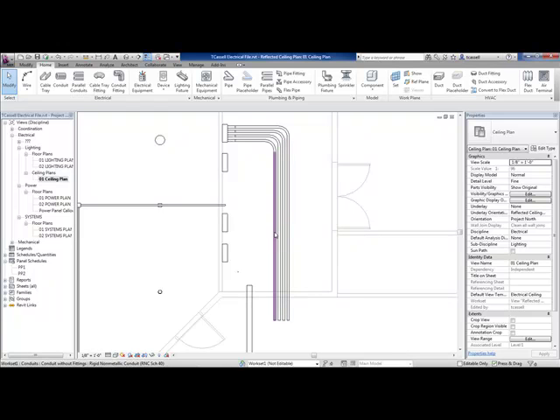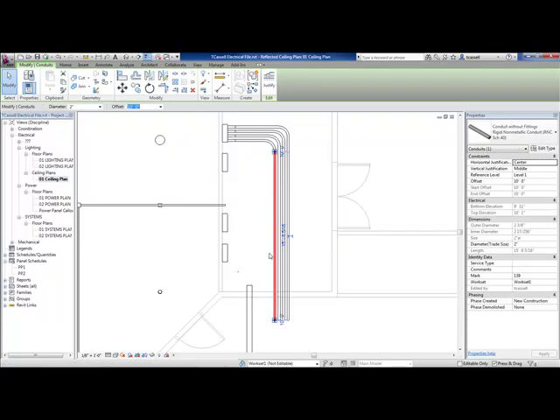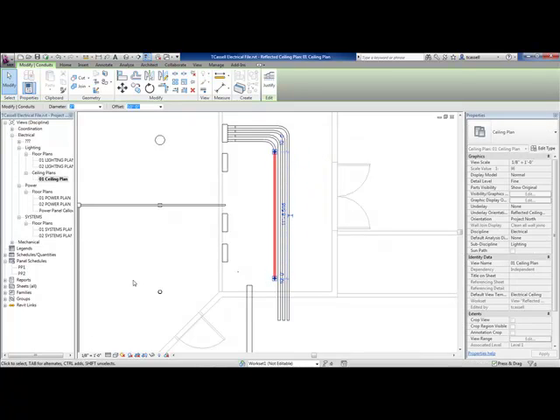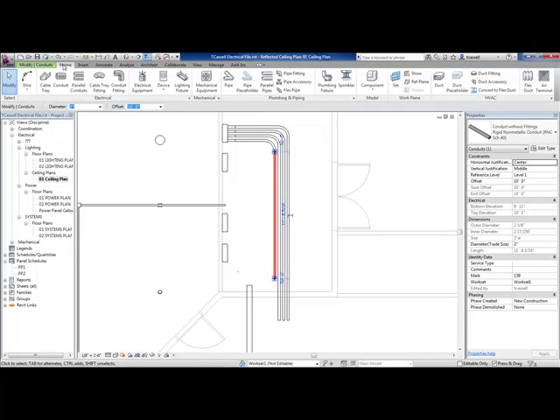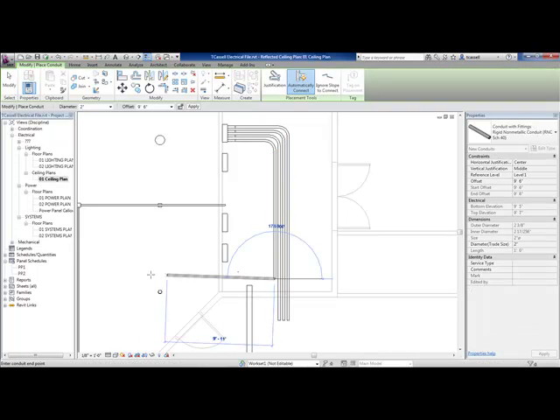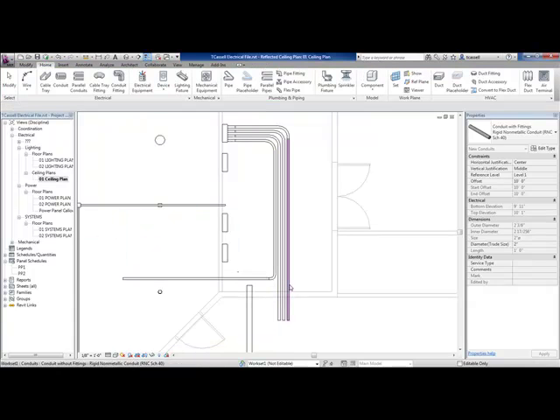You want to create the first run to the extent that you want to copy it first, because after the run's been copied, this is now considered separate Conduit Runs and they need to be modified manually separately. If this is now going to branch off and go to the left to feed these other runs, I can shorten this Conduit, grab more Conduit, and start running off in a different direction.